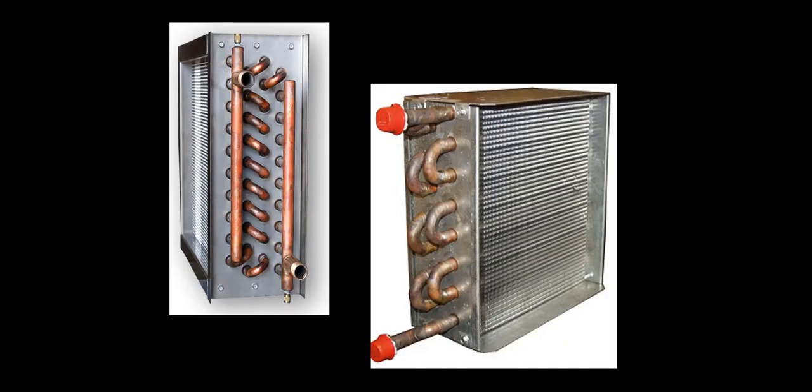Another aspect of designing water coils is the number of circuits in the coil. A circuit is an individual, unique path that the water will travel through the hairpins in and out of the coil. Circuits don't mix with each other. While the total number of hairpins and copper tubes inside of the water coil remains the same, the circuiting of the coil is how these hairpins and tubes are divided up. One circuit equals one pathway for water to flow through.